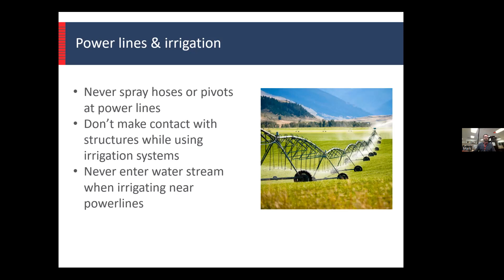Another method is induction - has anybody heard of that? In rare circumstances, induction can occur where equipment you're using can become electrically charged. It doesn't even have to touch the system, but the electrons in the air will start to build up a charge, especially if you're right underneath the power line or tower. Ensure your irrigation system doesn't run parallel to a power line, because if you put two things in parallel, the energy wants to follow those lines together, so voltage can be induced into the pipeline beside it. Exercise caution when using any kind of equipment near transmission lines.